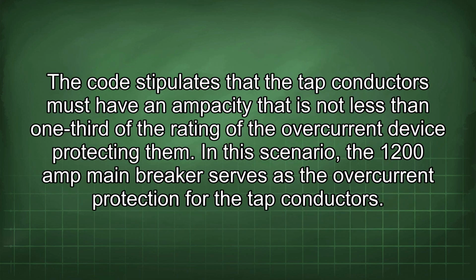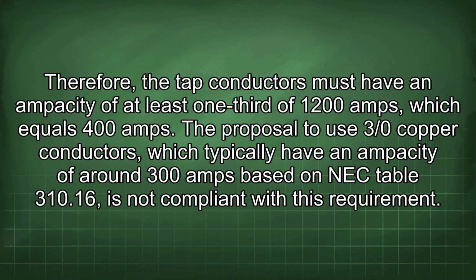The code stipulates that the tap conductors must have an ampacity that is not less than 1/3 of the rating of the overcurrent device protecting them. In this scenario, the 1200 amp main breaker serves as the overcurrent protection for the tap conductors. Therefore, the tap conductors must have an ampacity of at least 1/3 of 1200 amps, which equals 400 amps.